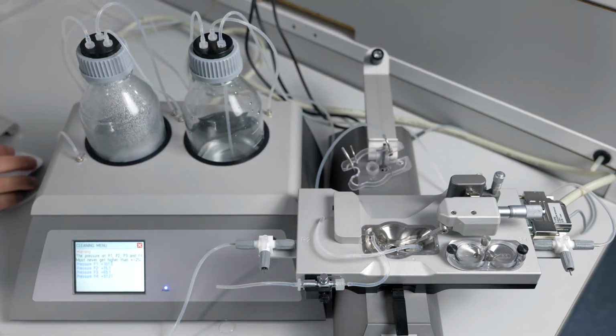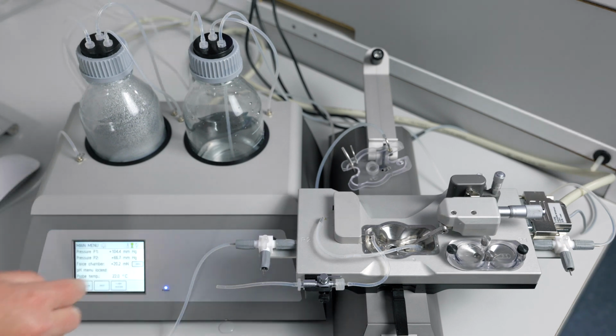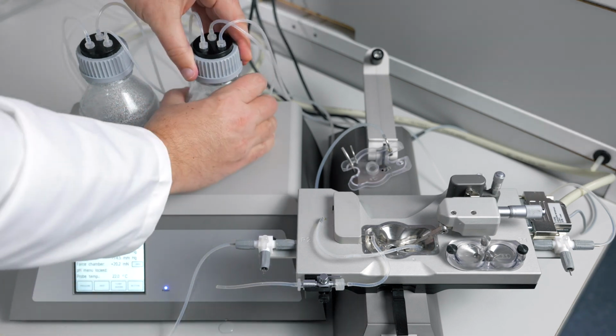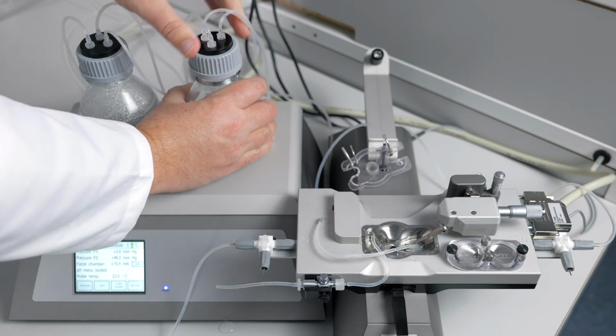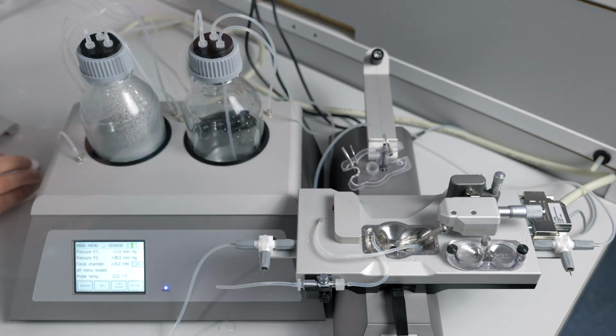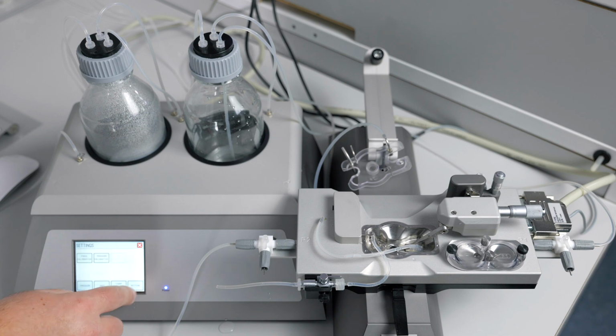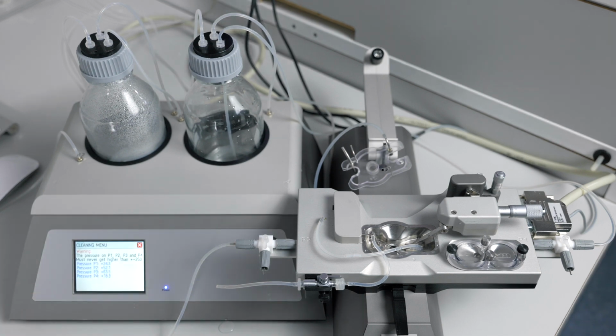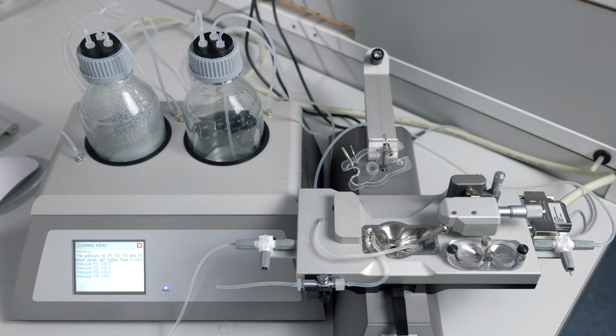And now it has been 10 minutes, so we can stop the cleaning procedure and empty the bottles of the distilled water. You can start the pressure and the cleaning menu again to push air through the entire lines. Again, the pulsation chambers should empty at this point. If you need to, you can open the bleed valves to help push the air into the pulsation chambers.